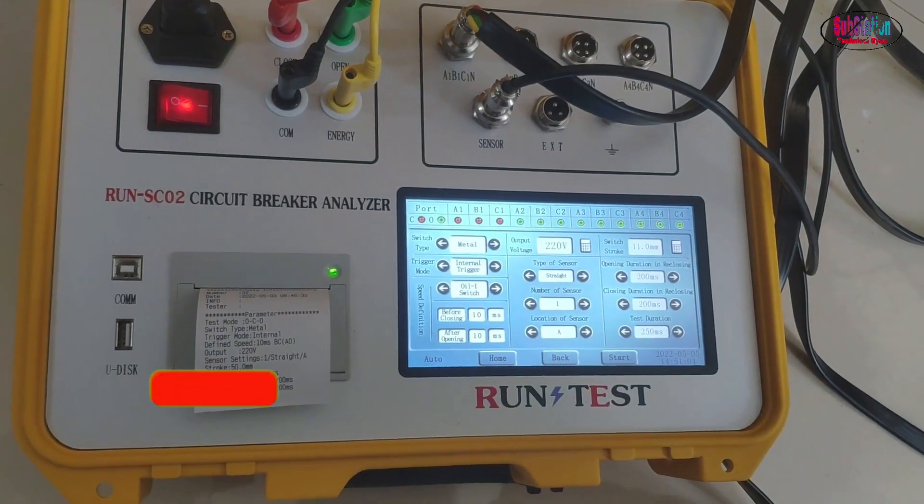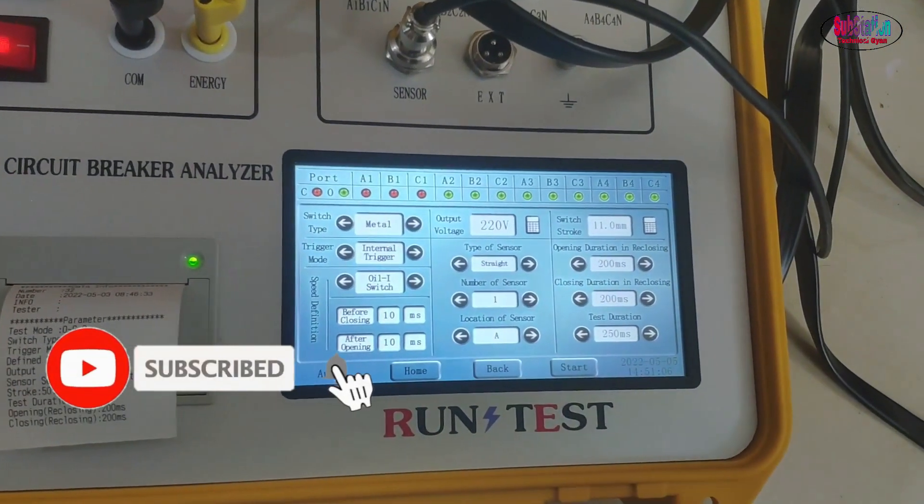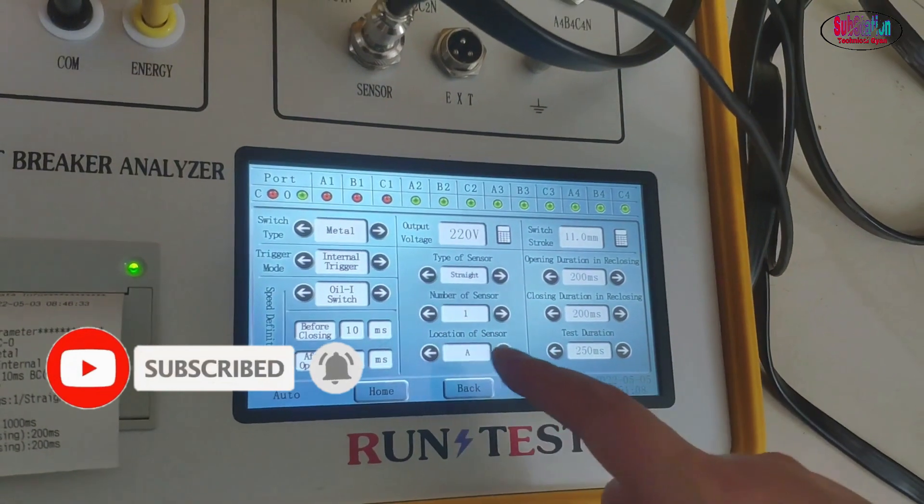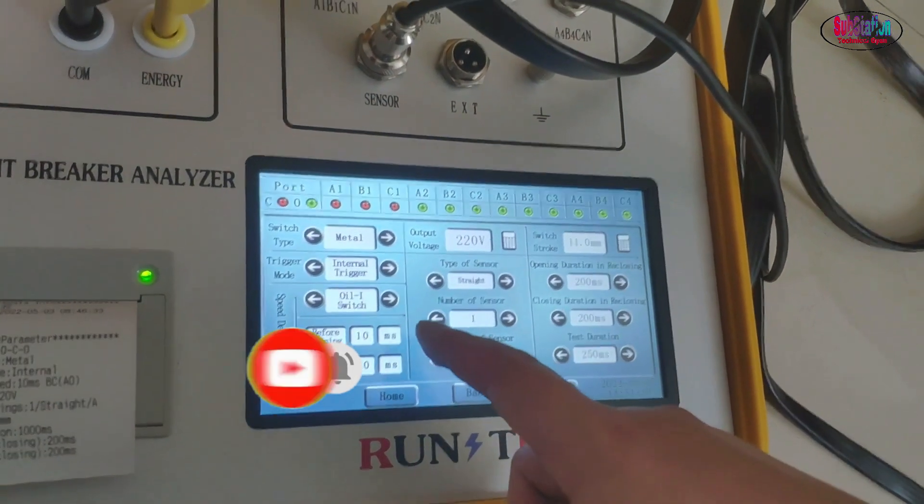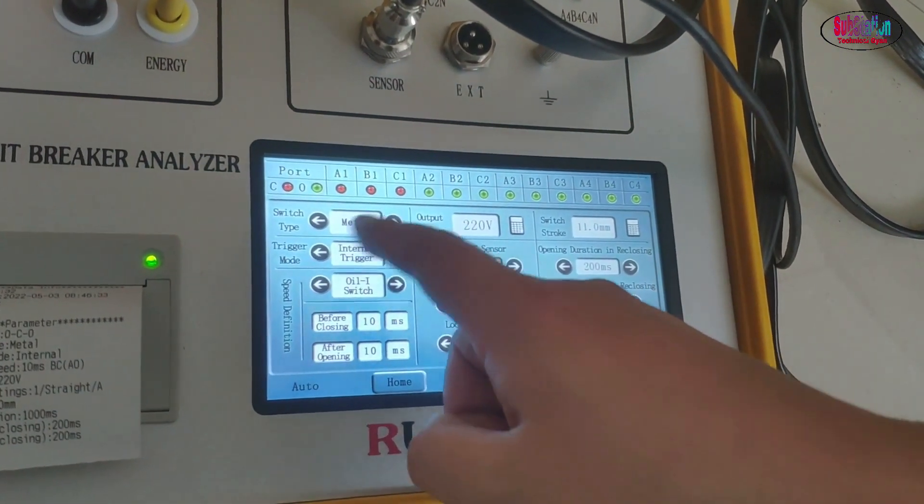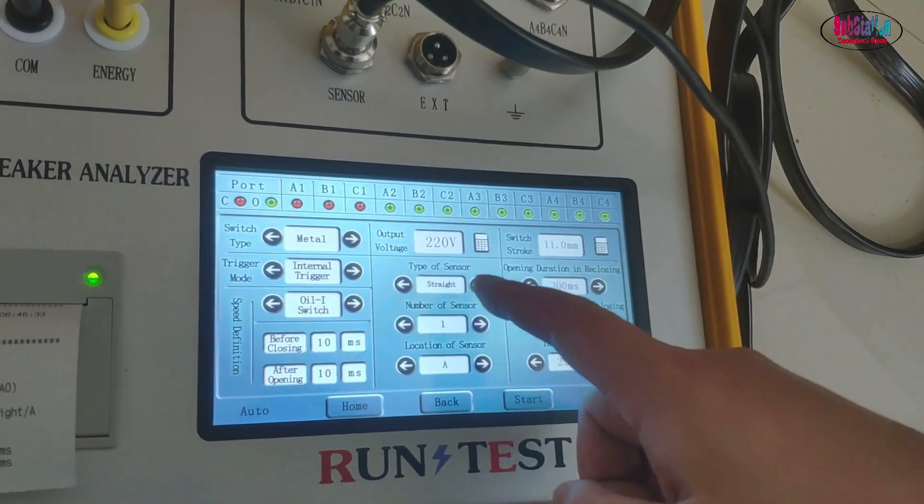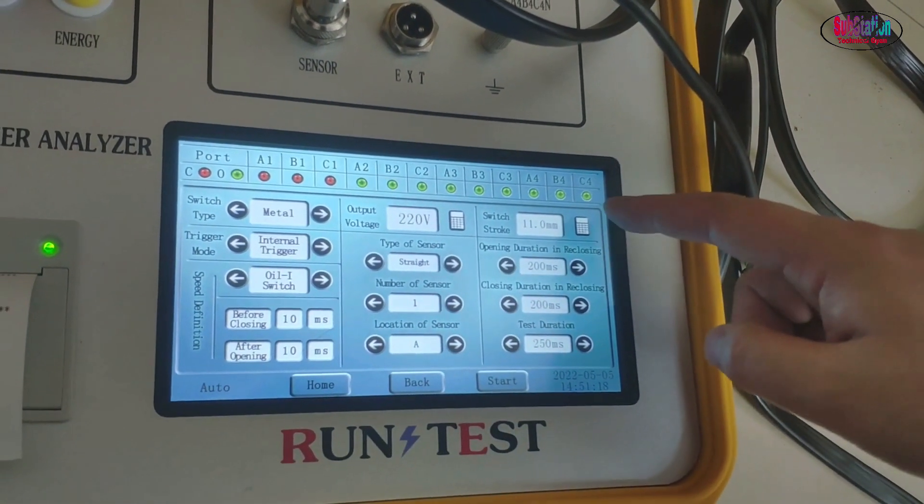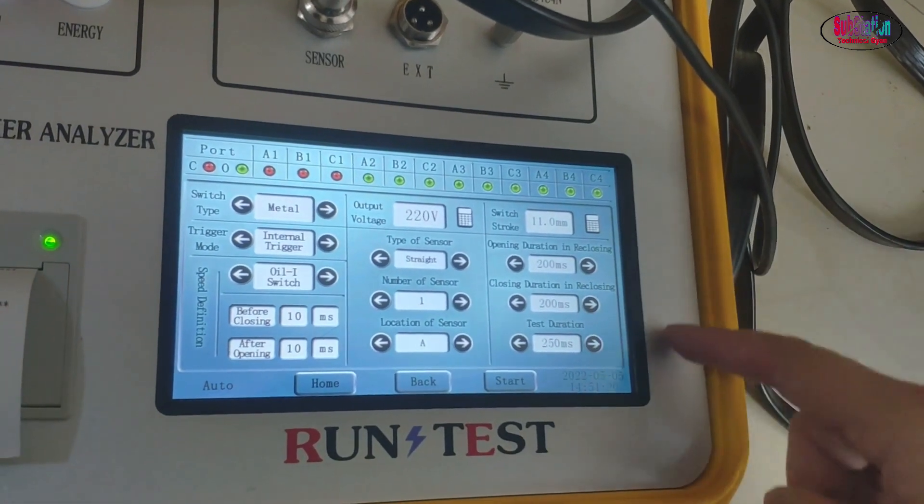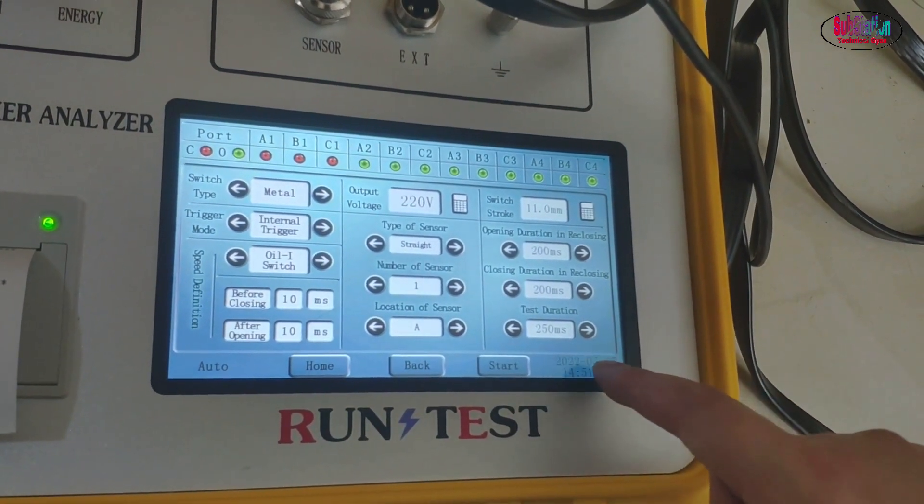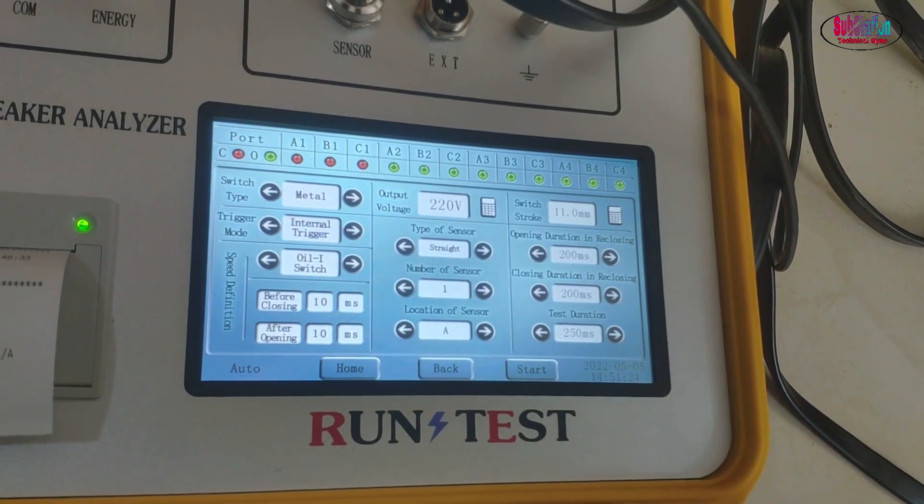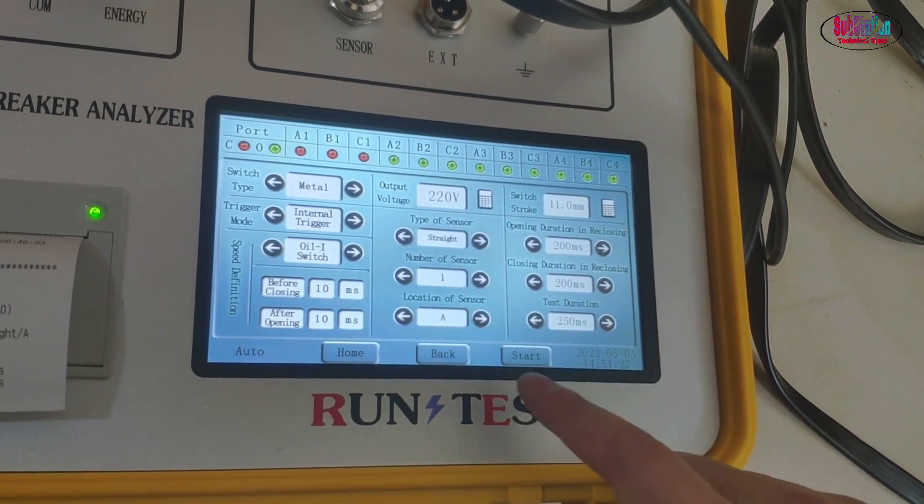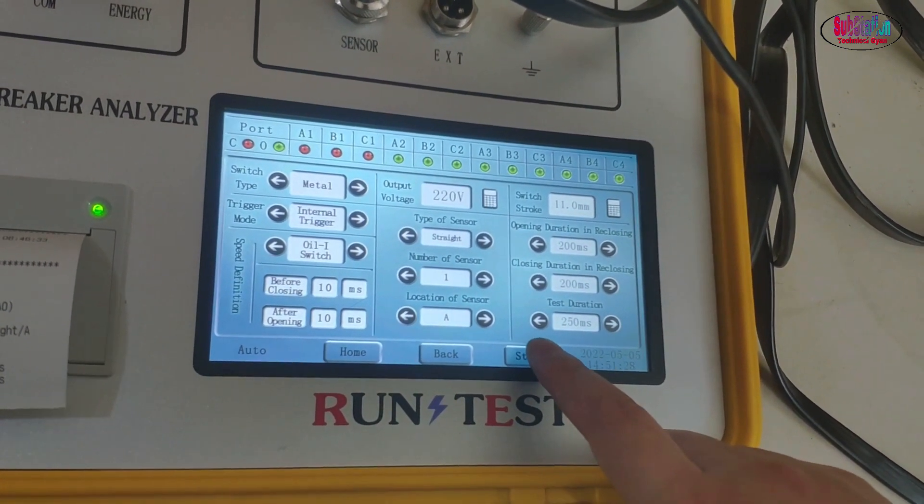We just set in the parameters. This is an oil circuit breaker and we use internal trigger. The output voltage is 220 and the stroke is 11 millimeters. We set the test duration around 250. We just press start.